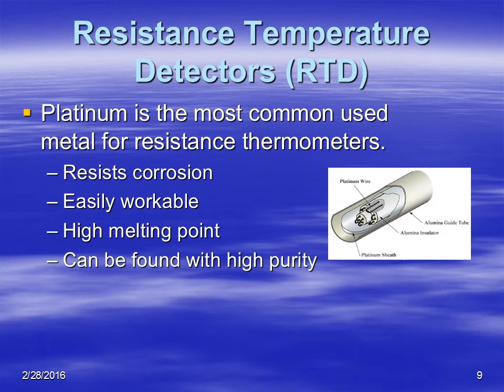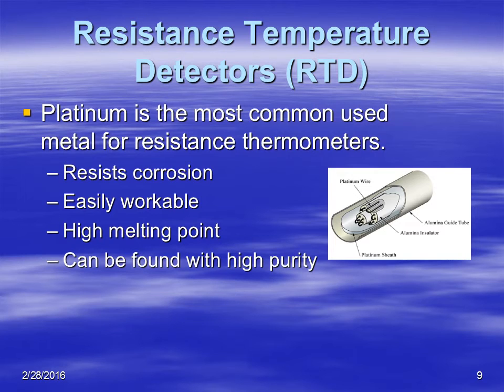The typical or most common metal used in RTDs is platinum. Usually these thermometers are called platinum resistance thermometers. The reason platinum is used is because it doesn't corrode very easily. Most of these sensors are outside exposed to the elements, so it's really important to have a metal that does not corrode. Also, platinum is easily workable, has a high melting point, and can be found with very high purity.